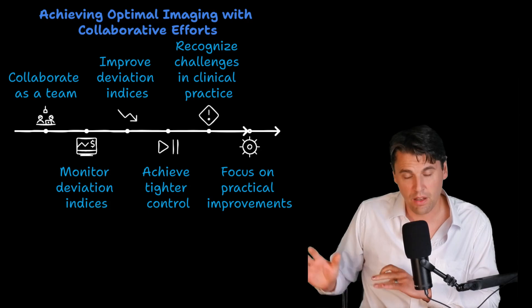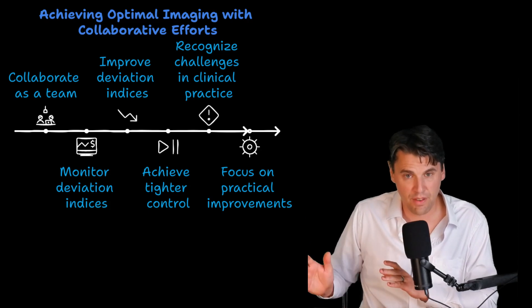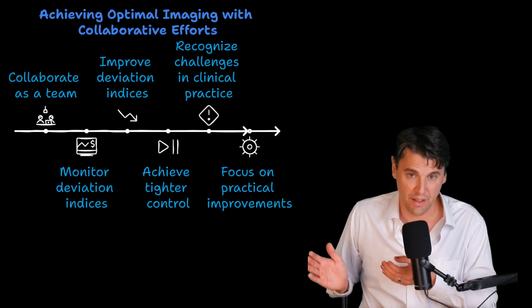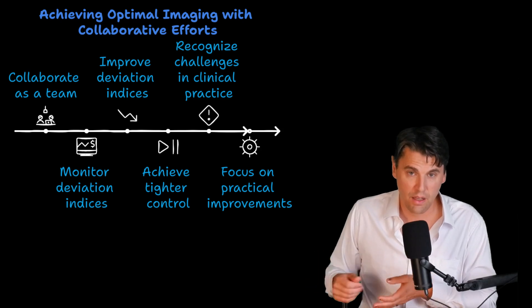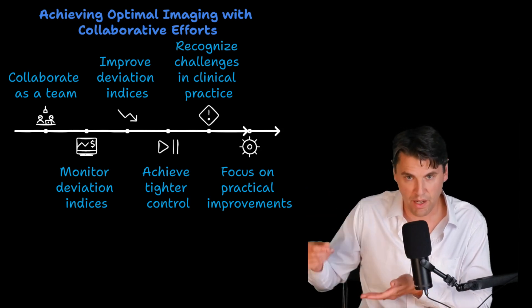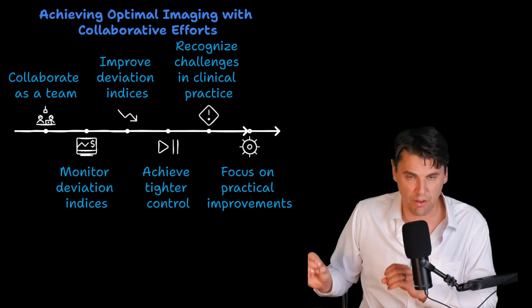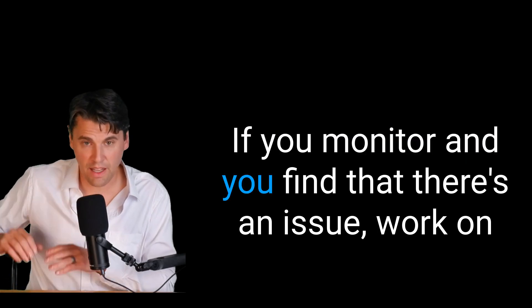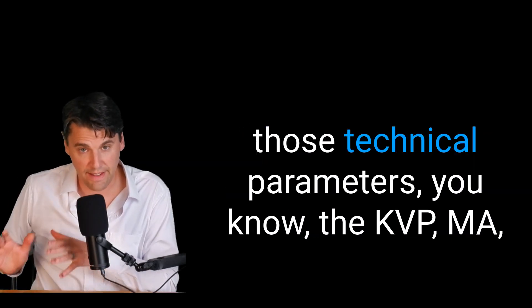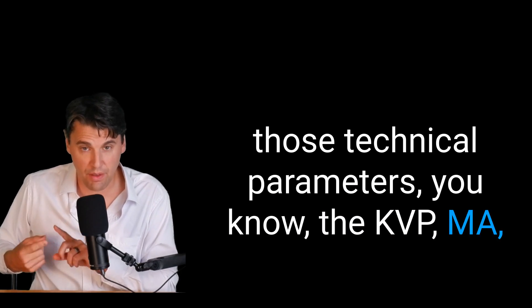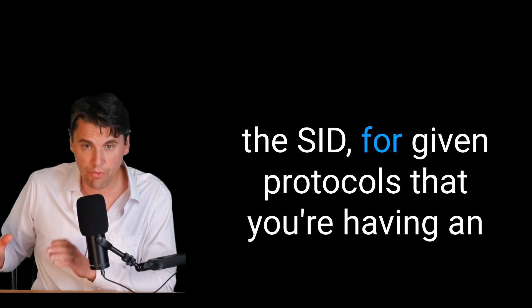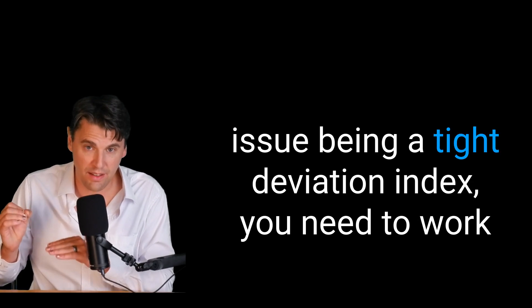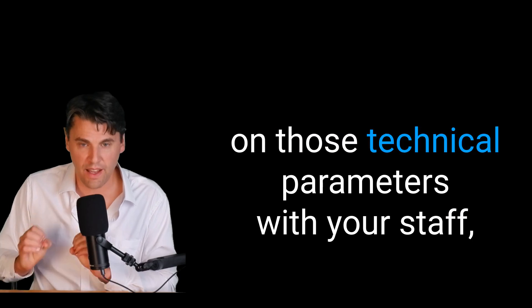In follow-up studies that have been done by the AAPM, for instance, it has been shown that these standards are actually quite difficult to achieve in actual clinical practice. In reality, what you want to do is focus on working on improvement, not necessarily strict adherence to those initial standards that were laid out. If you monitor and you find that there's an issue, work on those technical parameters, the kVp, mA, the SID.